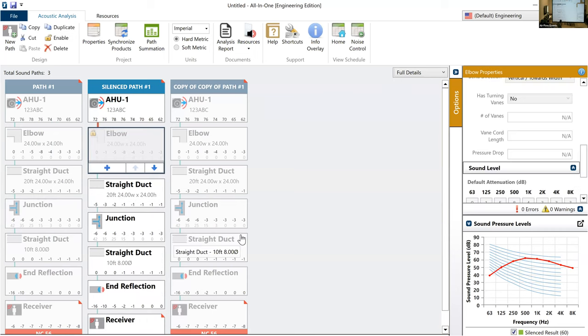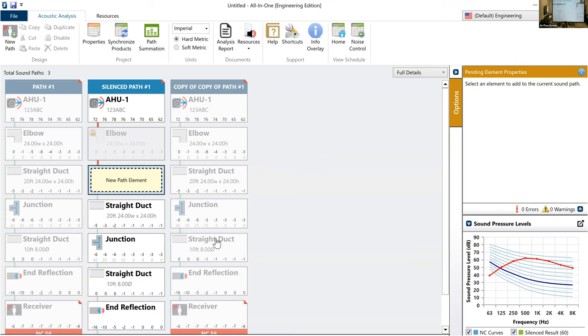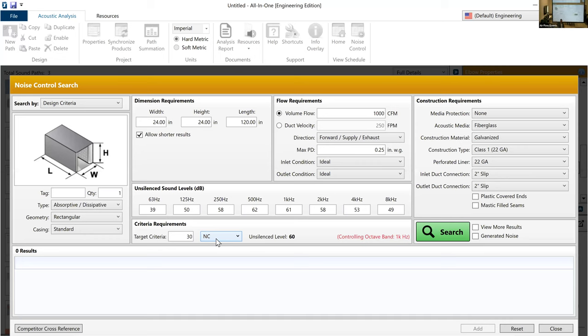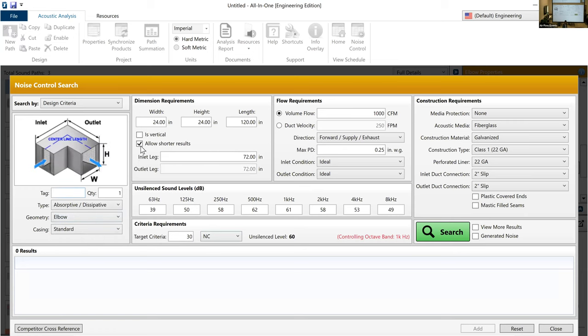One of the powers of this acoustic analysis software is that you're actually in the all-in-one software, which is where all of our silencer selections can be done. So in this case, if I want to pick an elbow silencer, you might have to configure it a bit the way you want it. Let's make it vertical like that. Maybe shorten it up a bit because I don't have a lot of space. Make that inlet leg a little bit shorter that's dropping down. And then what you'll see is that all of the information from the acoustic analysis, including the unsilenced sound levels and our criteria, got pulled over here.